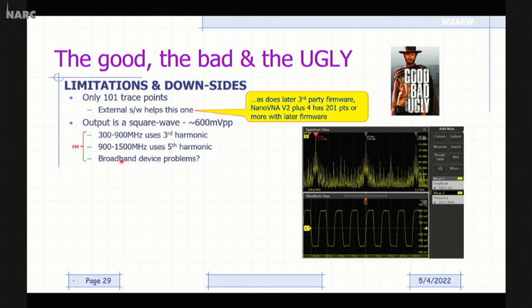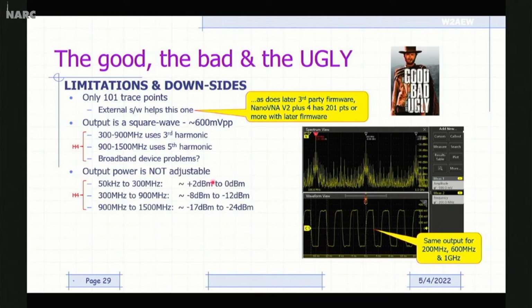So you have to think about, well, what device am I measuring? And is it going to have a problem with the fact that I'm hitting it with a square wave? In fact, if you look at this square wave, look at the frequency here, it says 200 megahertz. This 200 megahertz output square wave is the signal that's going to be used when we're measuring at 200 megahertz. It's the same exact signal that's used when we're measuring at 600 megahertz. It's also the same exact signal that's used when measuring at 1 gig, because it's using the third and fifth harmonic. So you have to think about the device you're measuring and whether it's going to like being hit with a square wave or not.